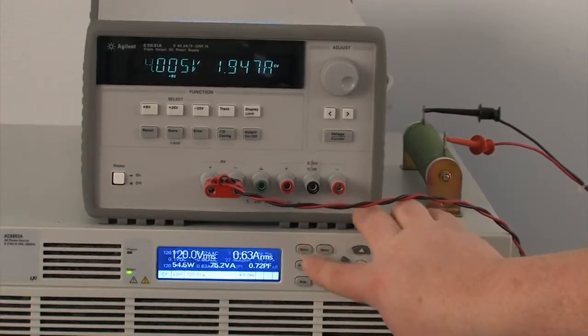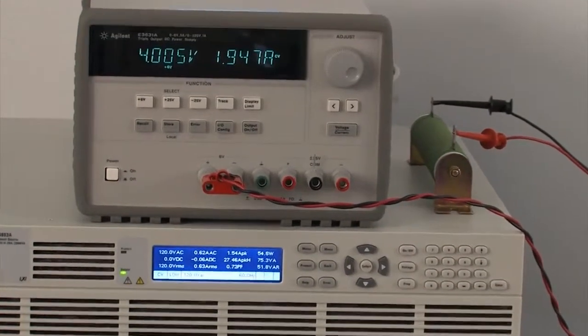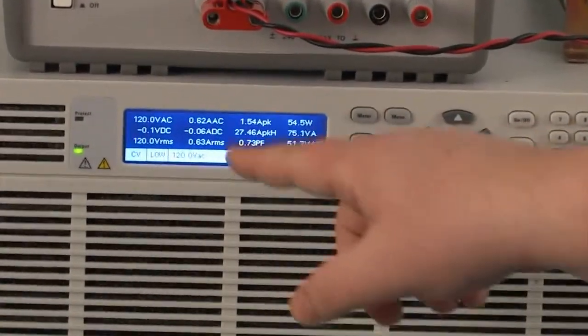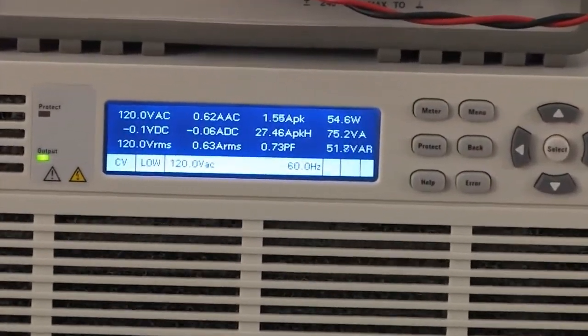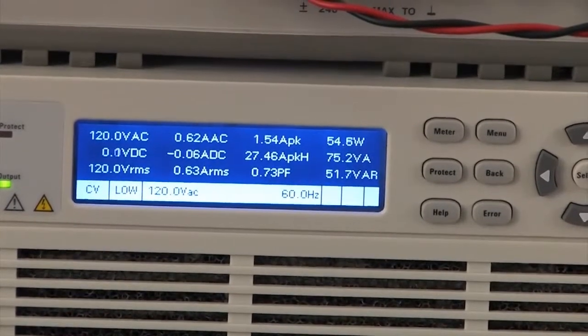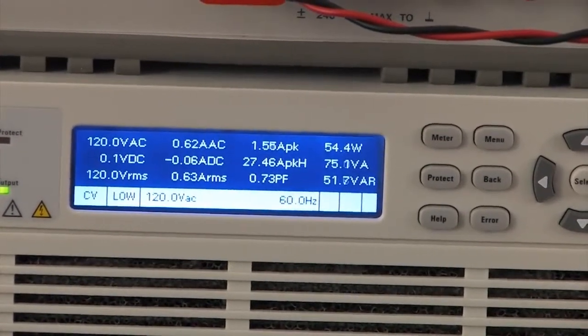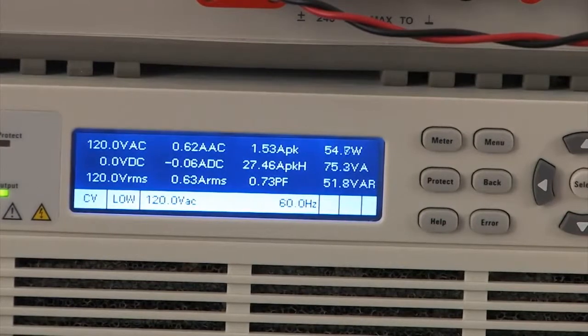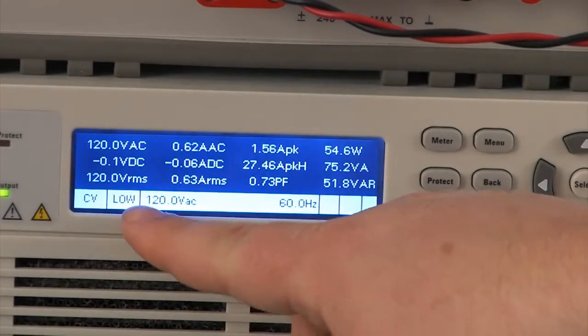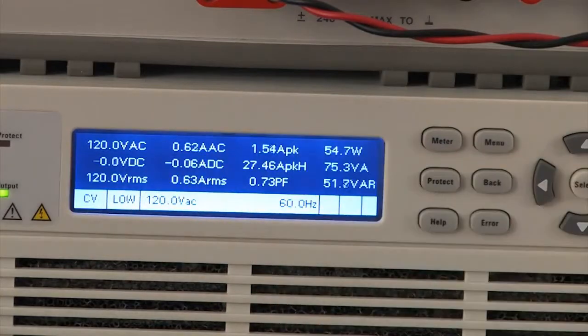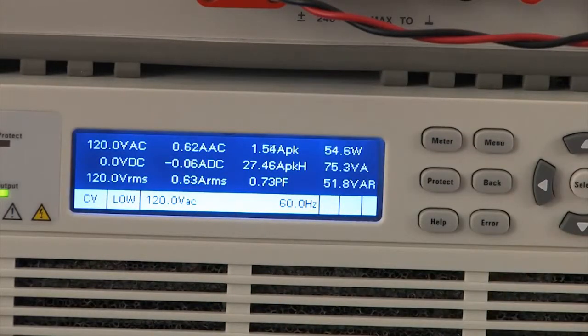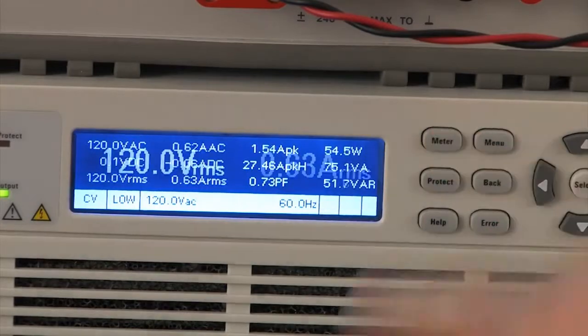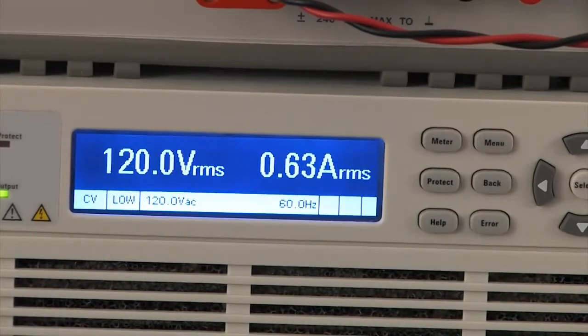I'm going to hit the meter button again, and you can see that there's a screen here with a whole lot of measurements on it. It's kind of hard to read if you're far away, but close up it gives you a whole lot of information in one spot. It's got all the power information, the peak current draw, the power factor, and the DC measurements, as well as the AC. And then if you hit meter again, you get back to our standard screen.